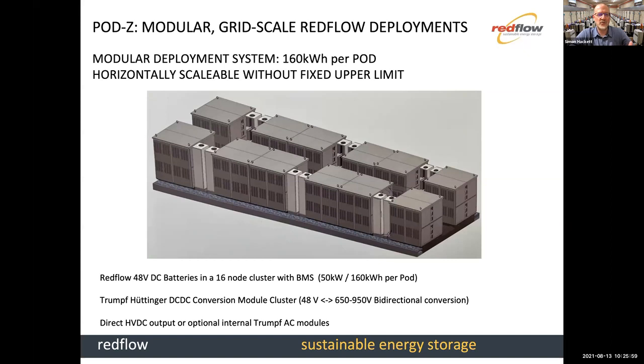The key product they make is something rather magical: a bidirectional power conversion unit called the DC 1010. It's a 10 kilowatt power conversion module that you can cluster. Each one can bidirectionally convert between 48 volts DC and, say, 800 volts DC, so about a 16 or 20 to 1 ratio of voltage conversion. When you step the voltage up by a factor of 20, you step the current down by the same factor, similar to a transformer in AC, but in DC you need innovative electronics to do it efficiently. These guys make that innovative electronics, and we've been working with them for quite some time.